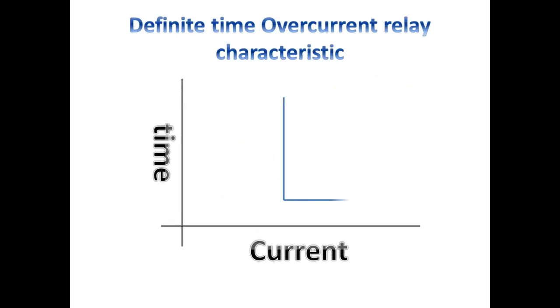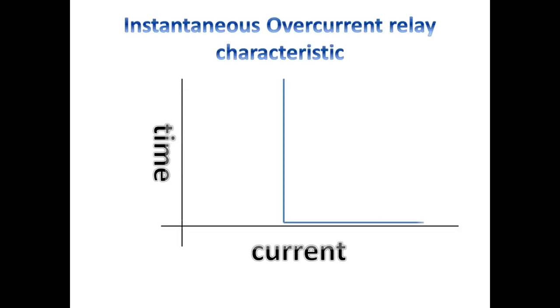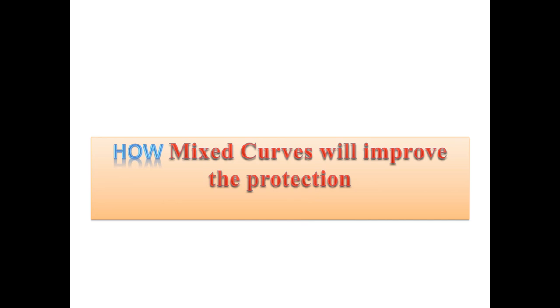This is the characteristics of the definite time over current relay. Once the actual current touches the ISET value, the relay will wait the set time and then trip. Looking at the instantaneous characteristics curve — once the actual current reaches the ISET value, it will start to give a trip command within milliseconds.